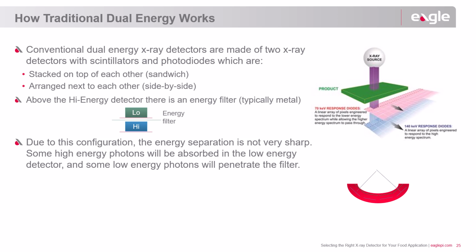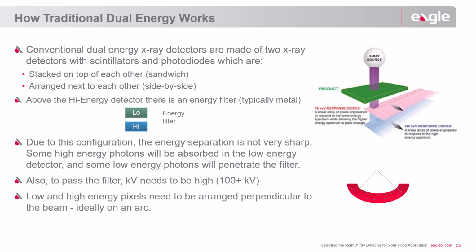Consequently, this setup allows for the determination of a material's atomic composition by analyzing the ratio of detected high-energy to low-energy photons. To define the energy ranges clearly, one might set the low-energy threshold at 0 to 70 kV and the high-energy range at 70 to 140 kV. By taking this ratio, we can make informed conclusions about the material under examination. This filtering mechanism not only enhances the accuracy of the measurements, but also facilitates a more effective analysis of the material's properties.